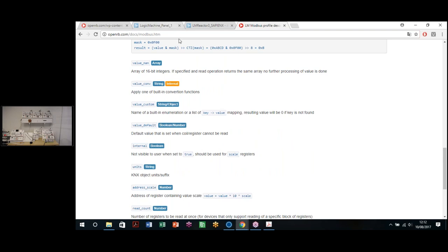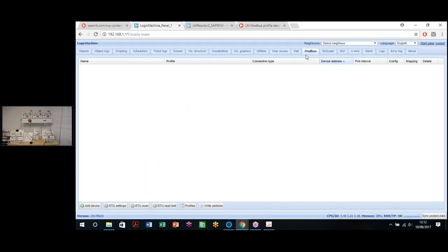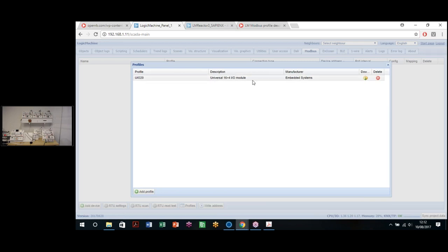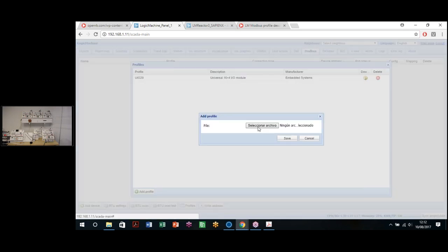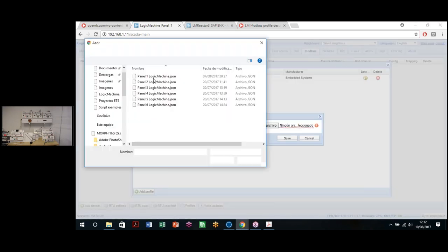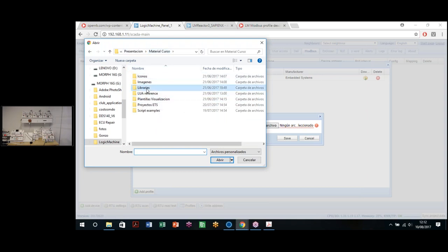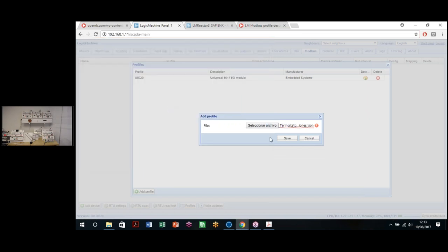So once we have this profile, we go to the LogicMachine, to the Modbus tab, and we select the Profiles button. Down in the center, we have a preloaded profile. It's the example that I showed you of the UIO 20, the Modbus extension IO module from LogicMachine. And we are going to click Add Profile. We click Add Profile and we look for the file that we have just created. In this case, libraries, Modbus. All this information, you have it in the material that we have uploaded for you. In this case, I'm going to use thermostat.